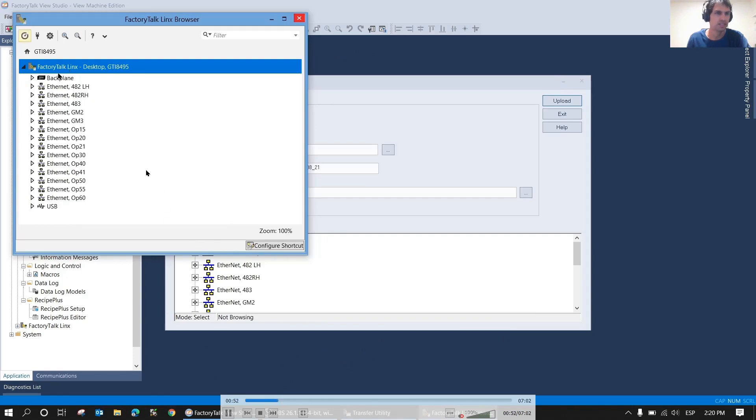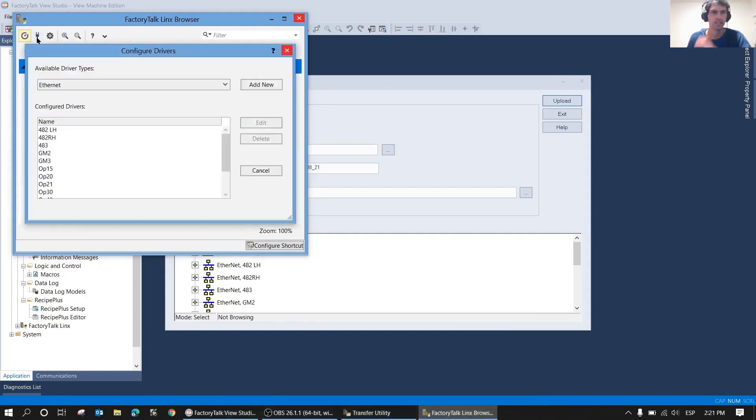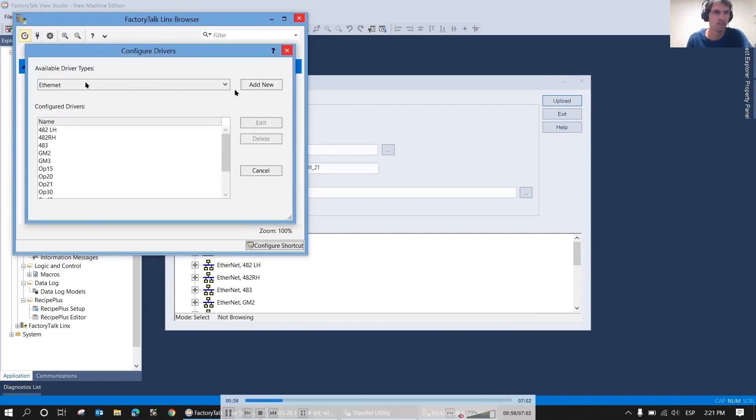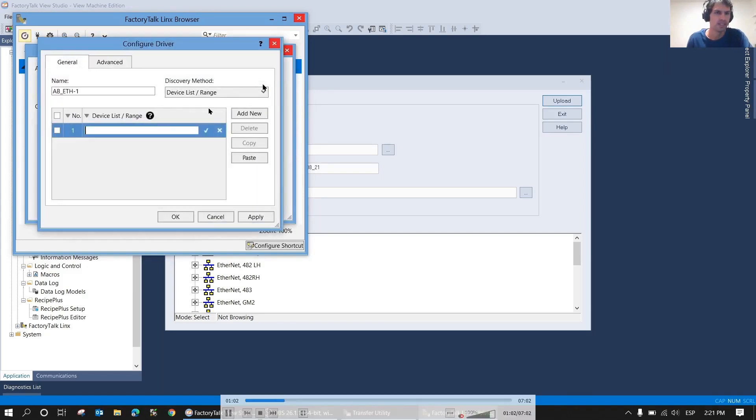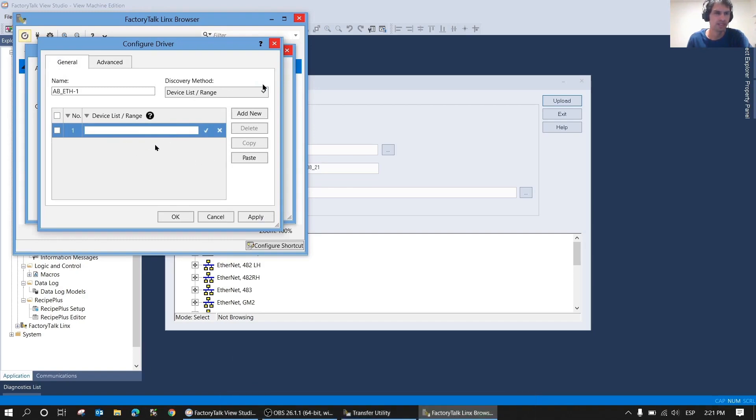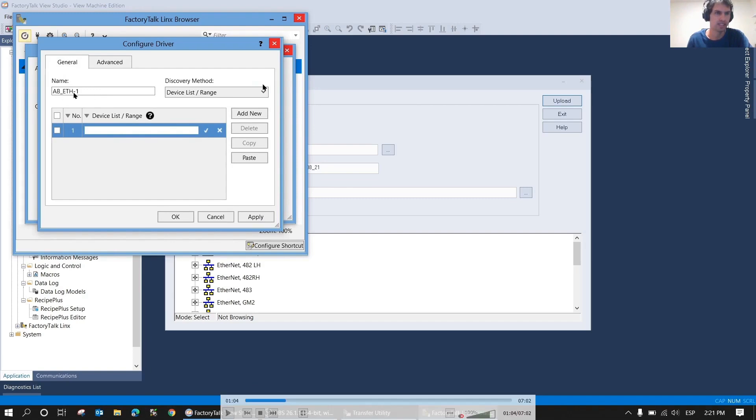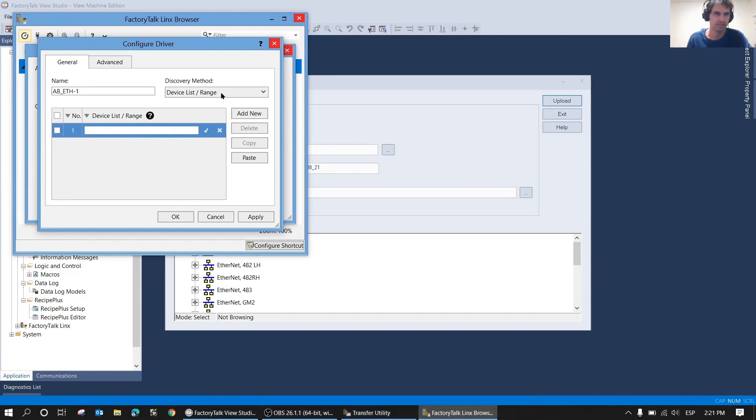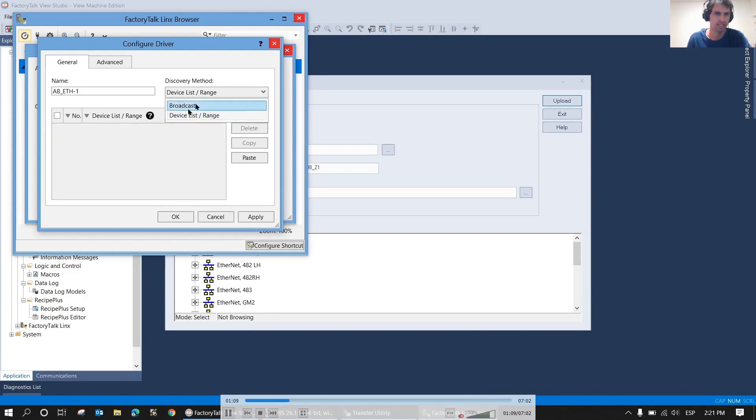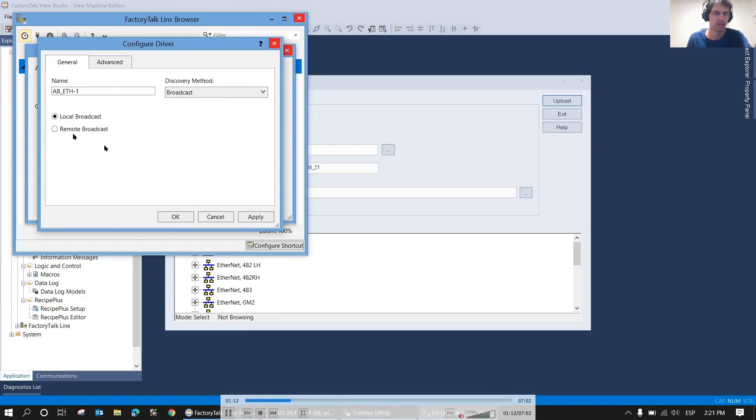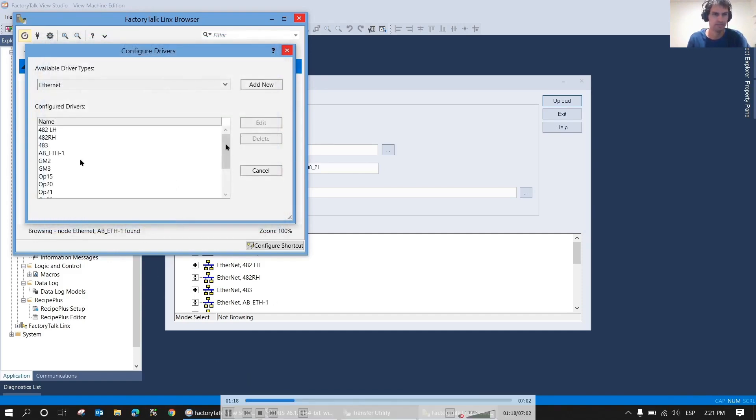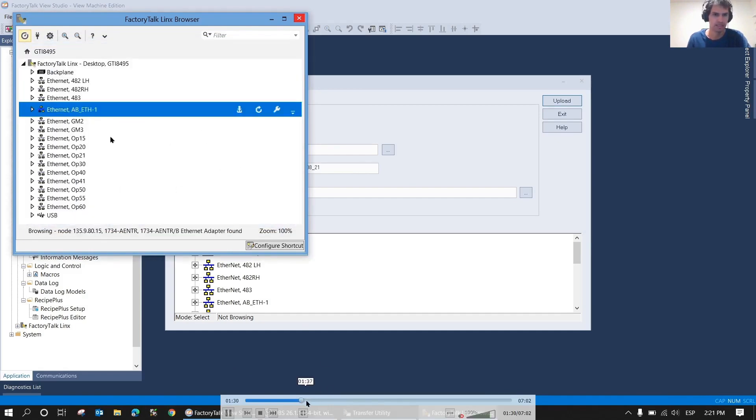Here in FactoryTalk Linx, we're going to click on the pin and add a new Ethernet. There are two options: device list range, which lets you add a range of IPs or specific IPs, or broadcast, which searches everything on that connection. In this case, we'll use broadcast. We could have simply added the IP of the PanelView, but I'm going to do it as a broadcast. We click OK, it has been added, and now we'll simply close it.